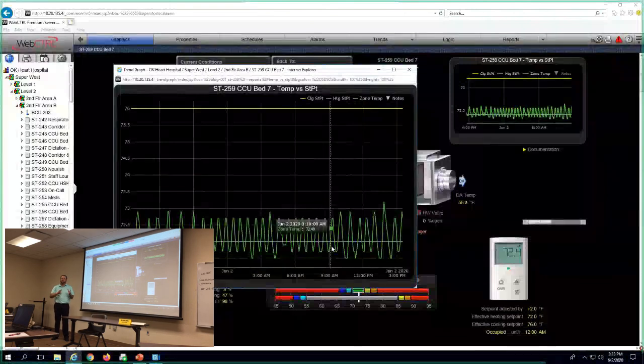It can be tuned and get closer. It's just, most humans can't tell you the difference between 71 and 72 degrees, or 73 and 71. Now, you drop down, it'll get much cooler, you go up, much warmer. I can tell you the difference between 75 probably and 69. But they've done tons of studies. ALC hired a company and did studies, and overall they say 74 to 70 is the most efficient place to run a building. Of all these studies, that's where you get the most efficiency out of your equipment.